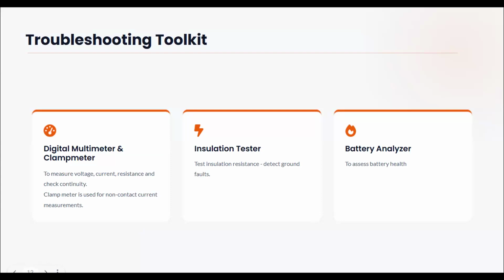There will be leakage to other parts of the material around that place, and if you touch it, you are likely to receive a shock. You think you are touching insulation. So it's important, and it's very dangerous to the appliance, as it is to the life of a human being. The battery analyzer is one other essential instrument that gives you peace of mind when you want to troubleshoot a battery. It can be complex if you don't have this instrument, because you won't be able to test properly. You will need to put on load and you'll be disturbing your clients.